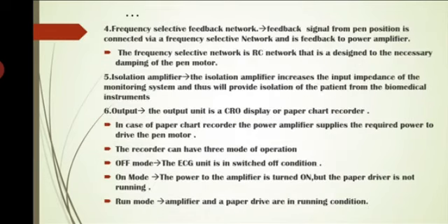Frequency selective feedback network. Feedback signal from the pen position is connected via a frequency selective network and is fed back to the power amplifier. The frequency selective network is an RC network that is designed to do the necessary damping of the pen motor.